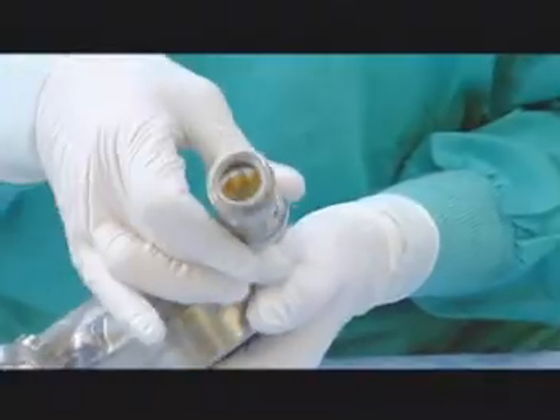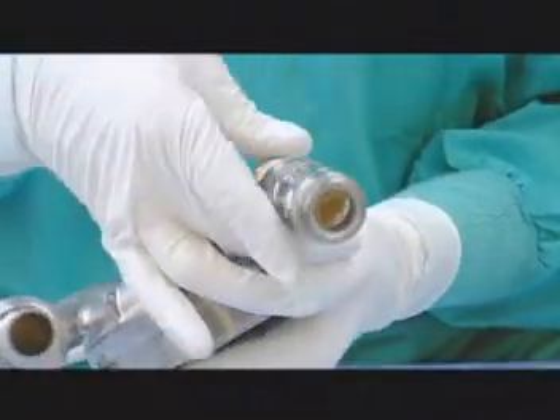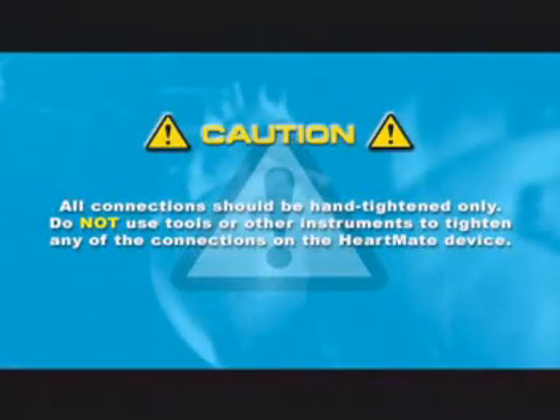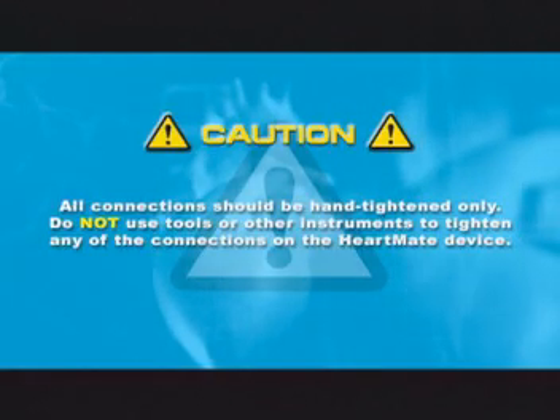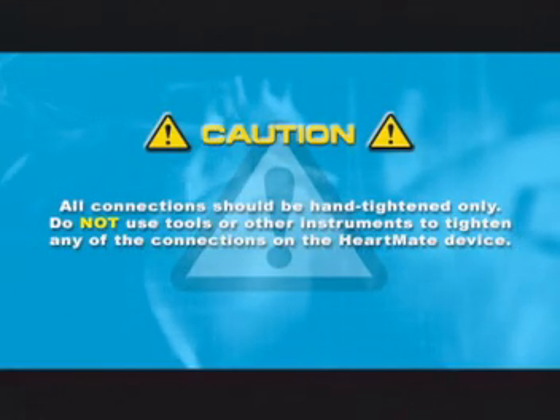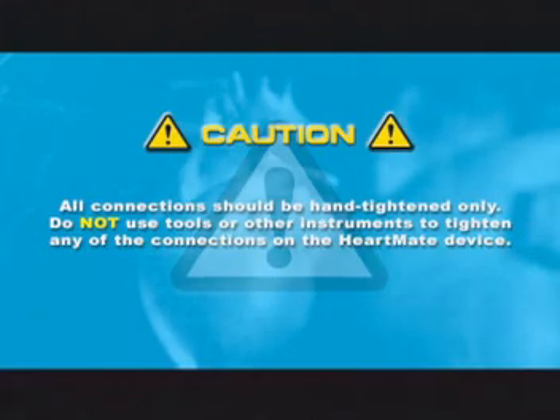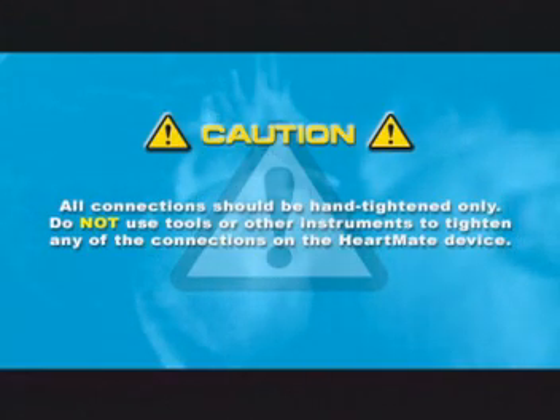Turn the screw ring at the base of the outflow valve conduit clockwise until you hear a clicking sound, then continue turning it until the connection is tight. Caution: all connections should be hand-tightened only. Do not use tools or other instruments to tighten any of the connections on the HeartMate device.